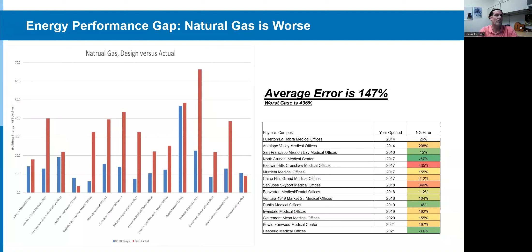I think our design community likes to specify a high efficiency condensing boiler and call that the answer. So on this project we specified one, and since we had gas metering and BTU metering in place, we measured the actual system efficiency. That 94% boiler had actual efficiency closer to 30%. It has everything to do with system design, flow, turndown, and delta T's, and frankly our design engineers are just not good at designing hydronic systems in a way that makes 94% realizable.